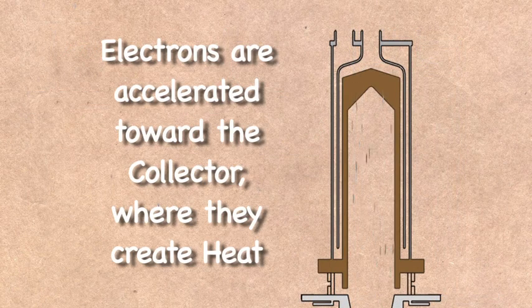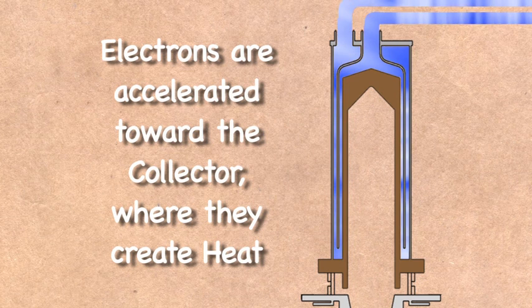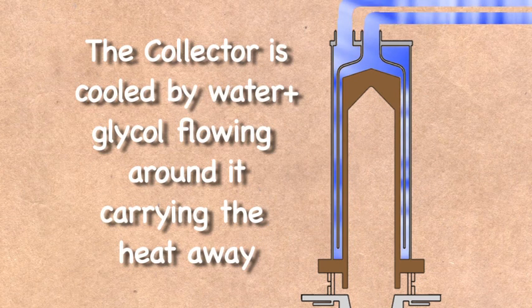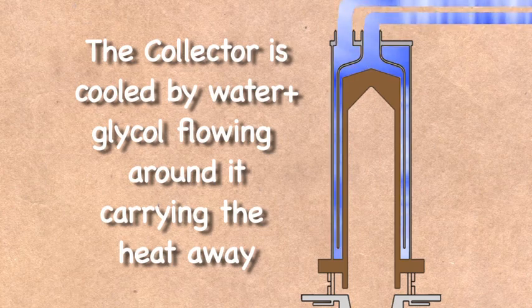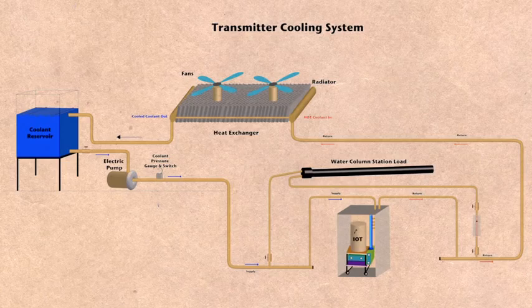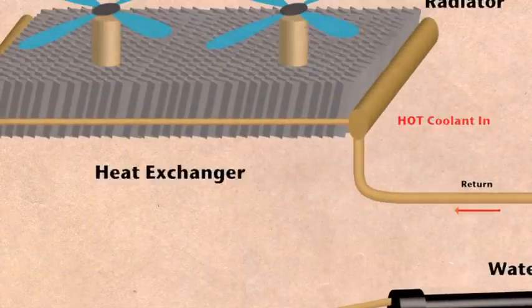As the beam of electrons strike the collector, it must dissipate that spent energy in the form of excess heat. It must be removed to keep the collector from melting. So the collector is surrounded by water, or a glycol water mix. The warmed coolant is sent to a heat exchanger where it is cooled and returned to the IoT.